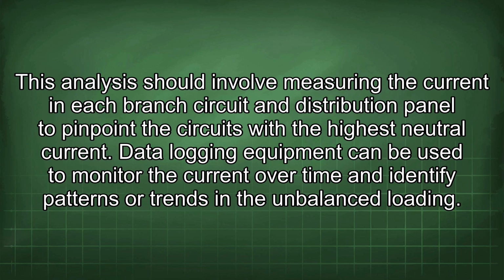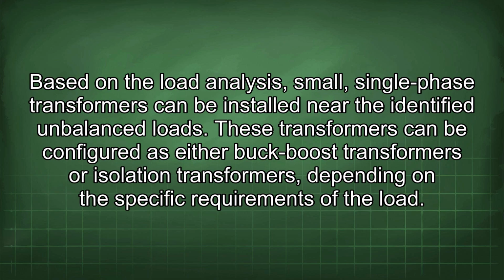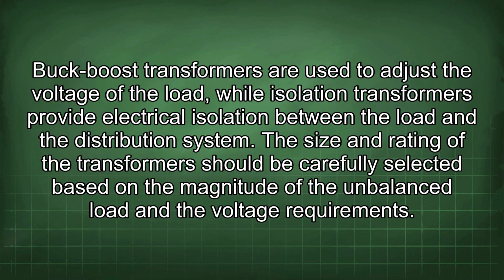in the unbalanced loading. Based on the load analysis, small, single-phase transformers can be installed near the identified unbalanced loads. These transformers can be configured as either buck-boost transformers or isolation transformers, depending on the specific requirements of the load. Buck-boost transformers are used to adjust the voltage of the load, while isolation transformers provide electrical isolation between the load and the distribution system. The size and rating of the transformers should be carefully selected based on the magnitude of the unbalanced load and the voltage requirements.